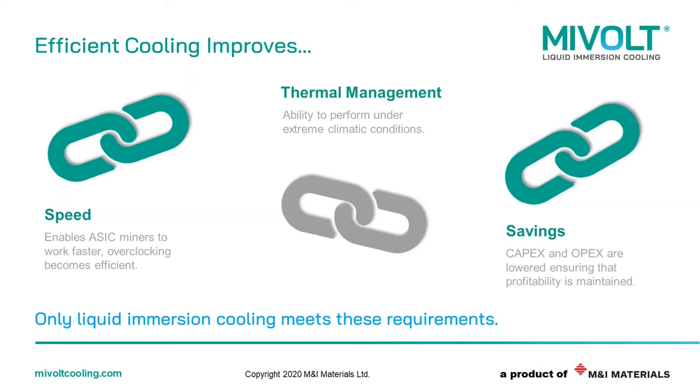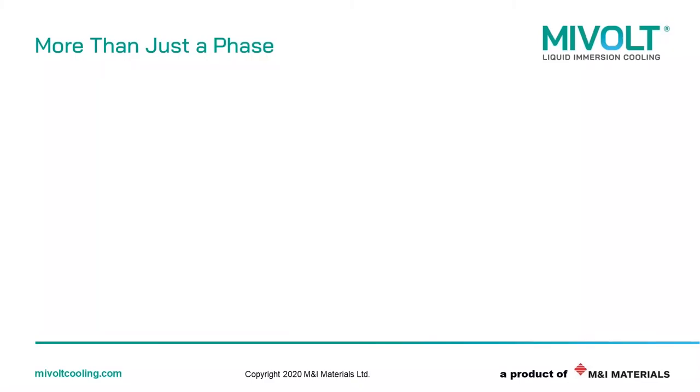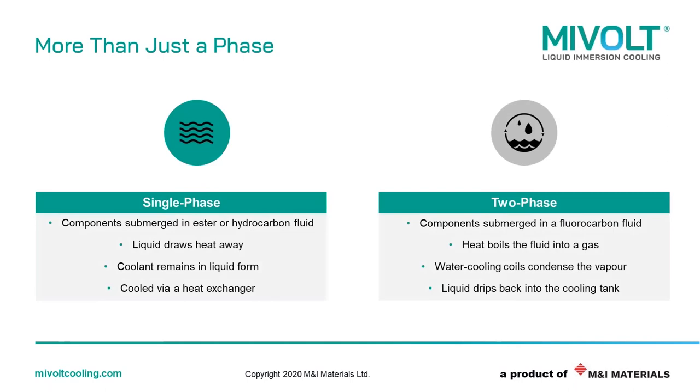I'll now hand it over to Mark Lashbrook, our technical lead, to introduce the MiVolt fluids. So we know that we need to improve thermal management, and immersion cooling is the answer. Essentially, immersion cooling is the placing of electronic equipment into a non-conductive liquid to provide enhanced heat removal. There are two methods utilised: the first, single-phase cooling, utilises a liquid with a relatively high boiling point, typically either hydrocarbon or ester-based. The liquid is a strong dielectric to prevent shorting of equipment, with excellent thermal conductivity and direct contact with components to draw heat away effectively, then circulated through a heat exchanger to remove that heat. This heat can then be easily recovered for secondary use, such as heating water or greenhouses in colder climates.